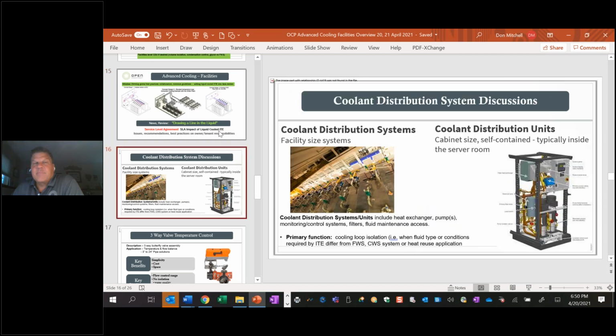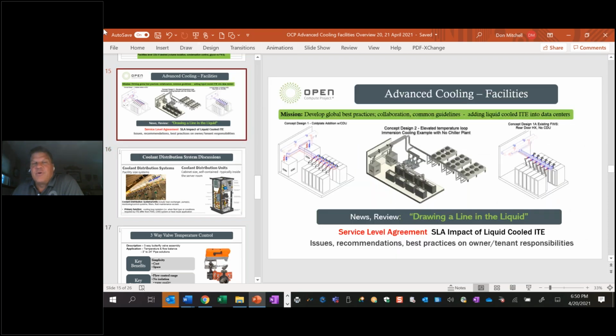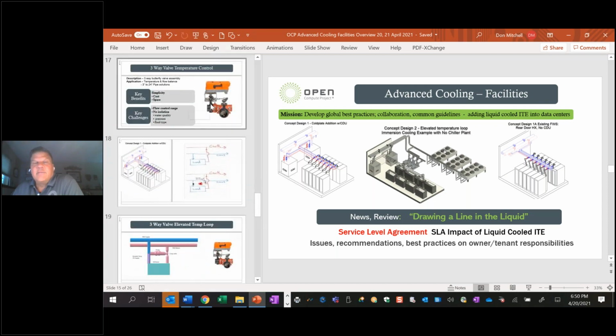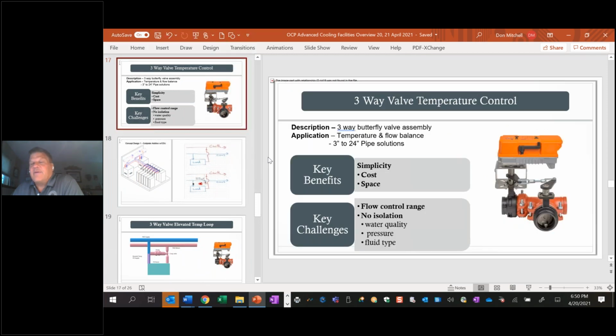One discussion that came up: if the only thing you need to do with a CDU is to raise the temperature of your facility water above dew point, that can actually be done with a 3-way valve.